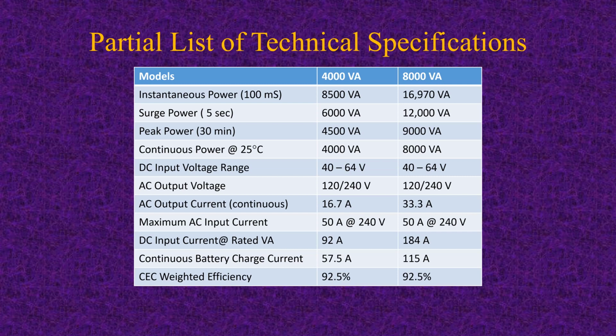You can bring in a lot of AC input current because most of it gets passed through to the standby loads. In each case, it's still 50 amps, whether it's an 8,000 volt amp or a 4,000 volt amp available for backup. Input current is twice as much for the one that's going to give you 8,000 volt amps. So you can see at 48 volts, 184 amps, that's pretty significant DC input current. You're using pretty fat wire to bring that in, and usually you're going to use battery cables that are more flexible and need special connectors, in fact, rated for batteries.